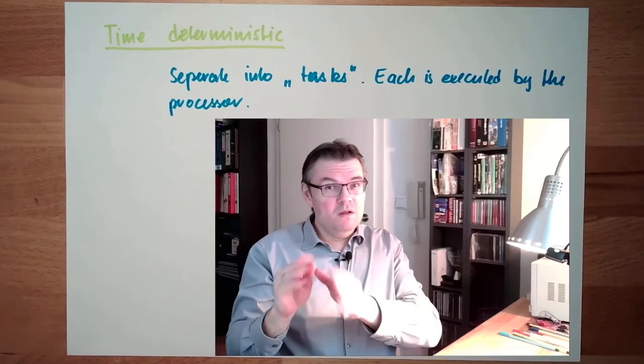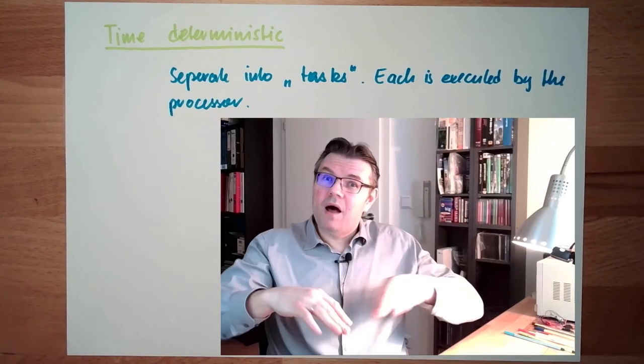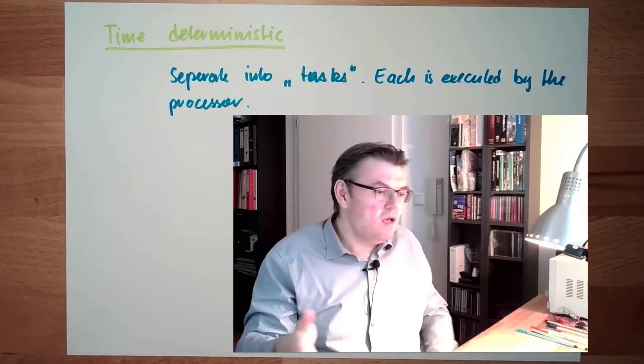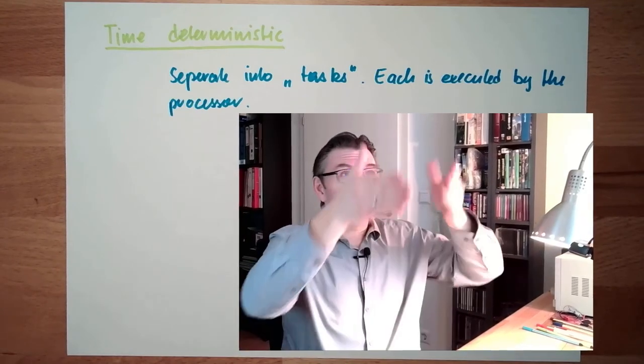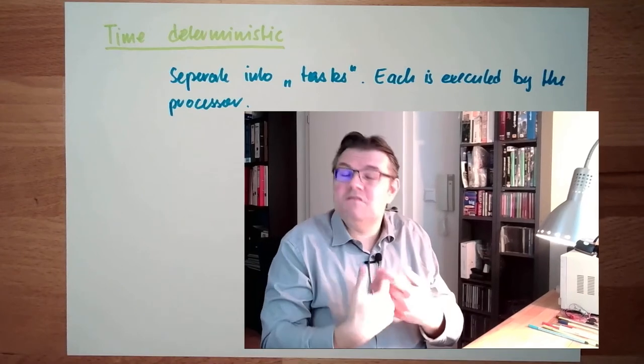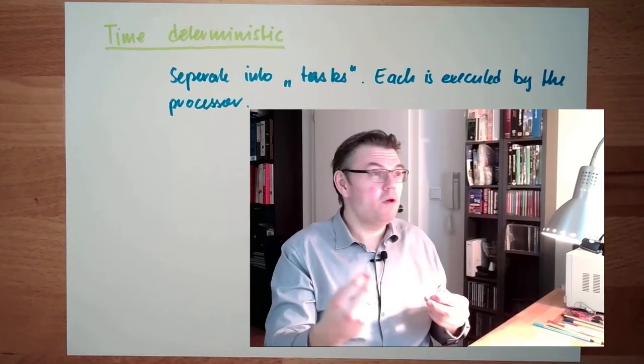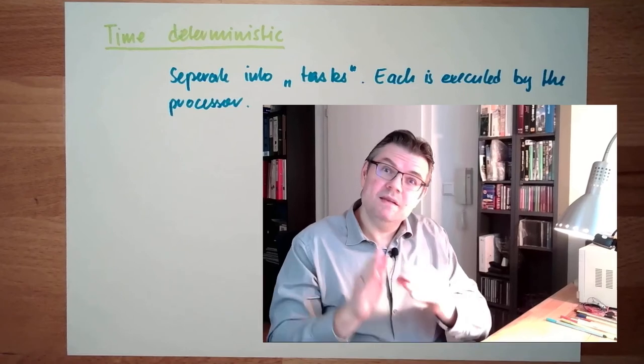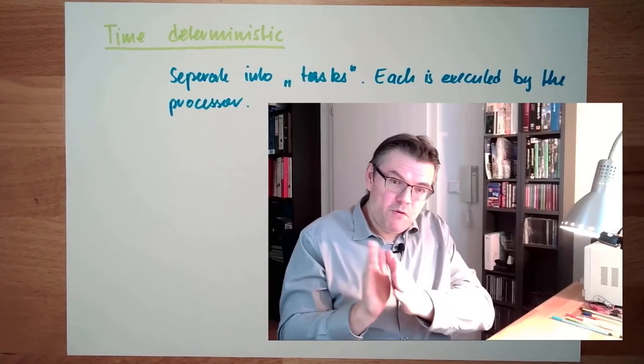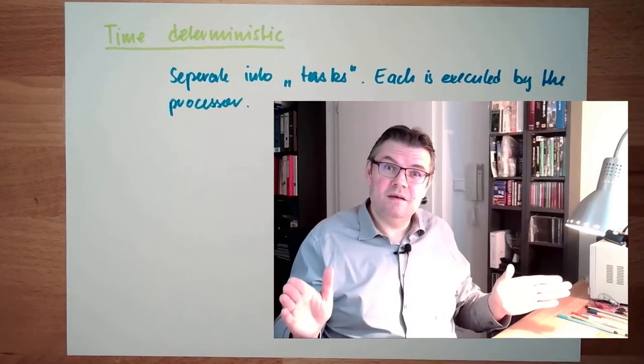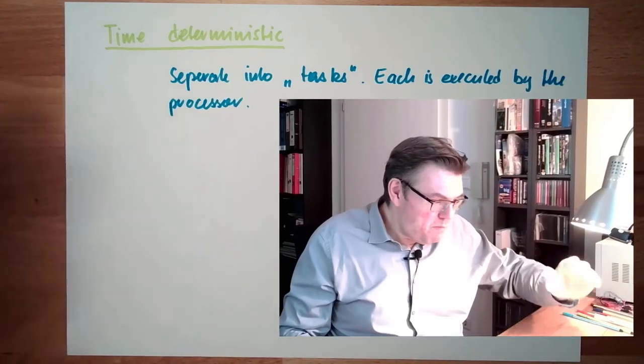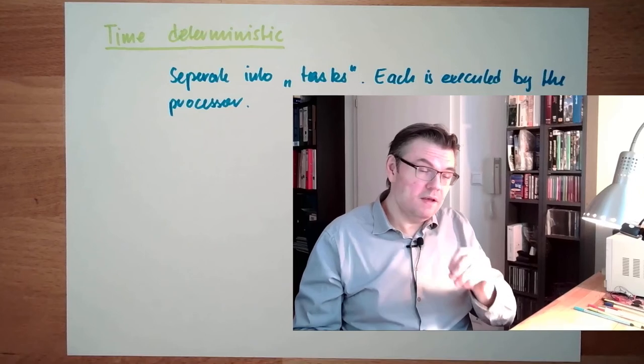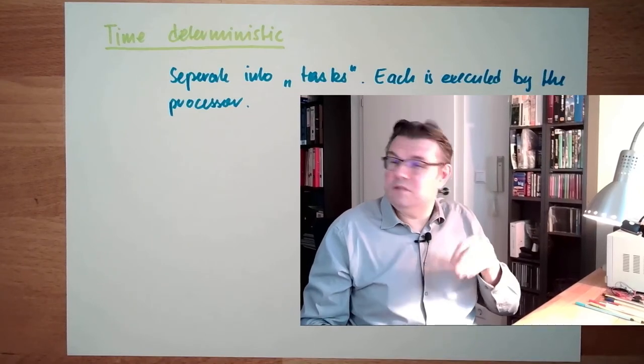This means if only one task is not operable, all other tasks are still working well and I can still operate my process. Imagine the outside temperature measurement is blocking the whole process — that cannot be. This time-deterministic behavior, this separation into tasks from the software perspective, needs to be part of a process control system. We need to prohibit one task from blocking all the others.